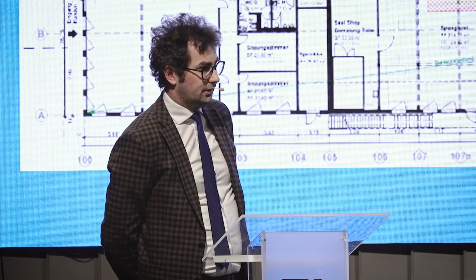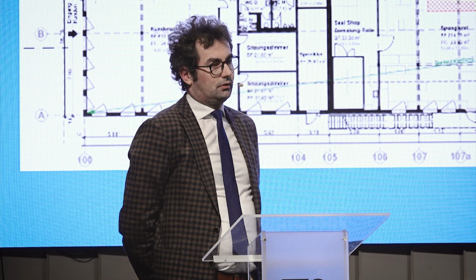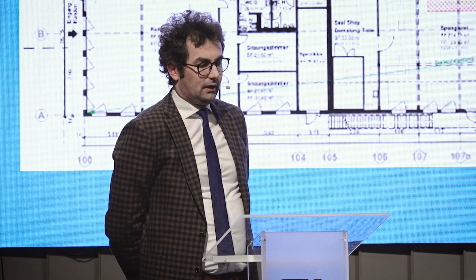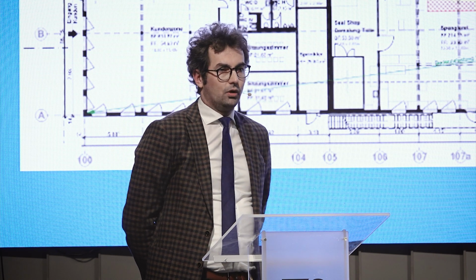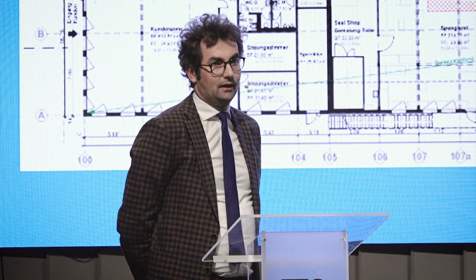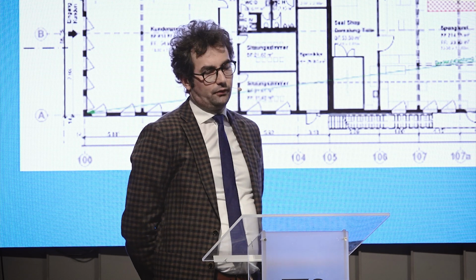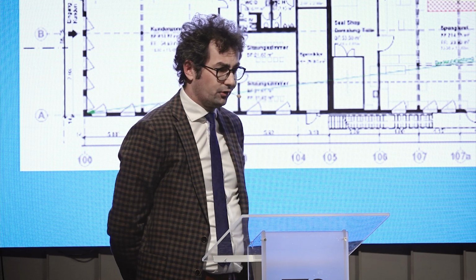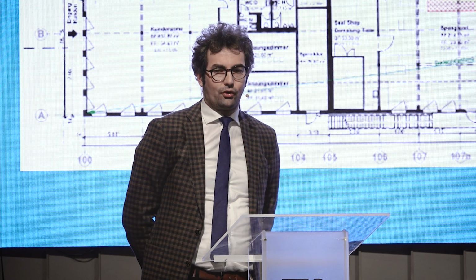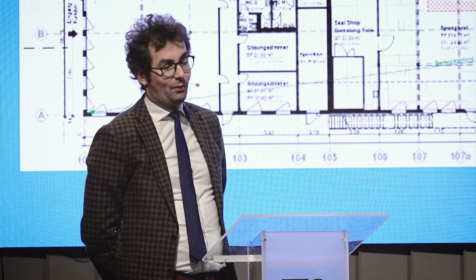There was a situation which we know from the same insurance, when after the activation of the foam system, the aircraft from the manufacturer, which was not in the fire, was declared a total loss. So you can imagine that in one false activation of the foam system, you can lose 16 aircraft. This was in one project. I cannot say that it is true for all foam systems in aircraft hangars, because this is only our experience in this project.